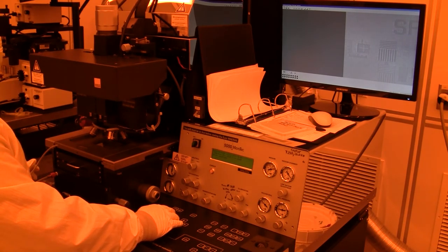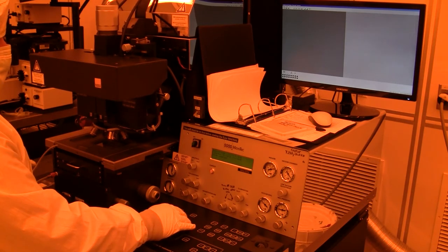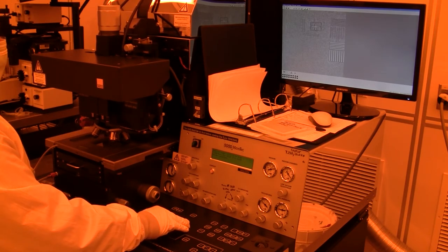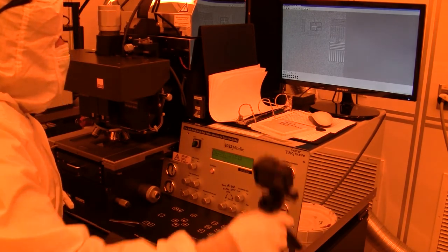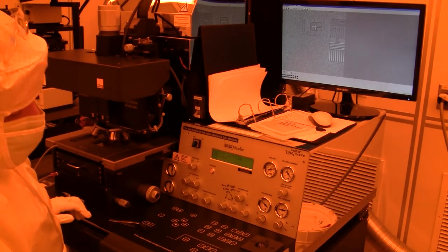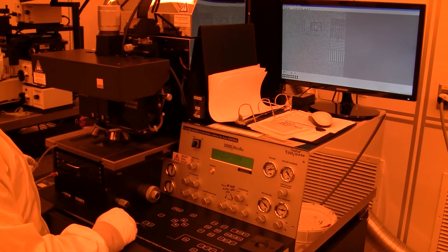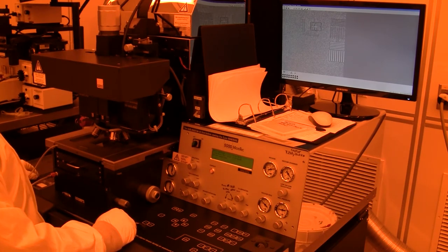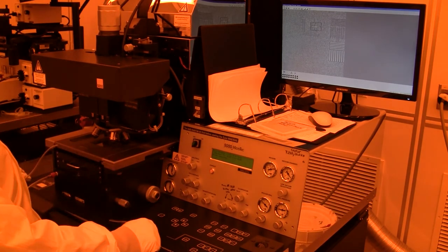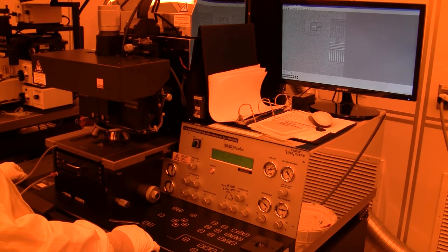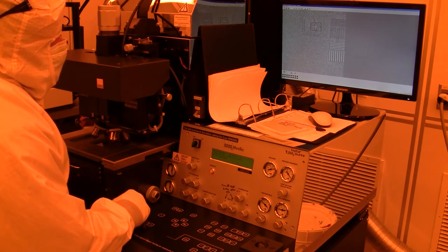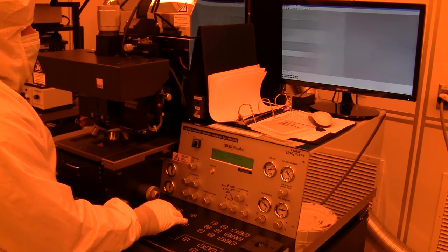Let's see what the left side looks like. Left side is okay, it's not great. Let me zoom in a little bit. So I'm going to do a combination of theta correction and translation. The reason I'm doing it this way, sort of iteratively, is because I can't image both sets of alignment marks at the same time, where I could if I had a four-inch wafer. It's just the way the optics are at the edge of the travel of the optics - we can't put the objectives that close together. So again, a little bit of theta, a little bit of translation. Let's go look at the other side.